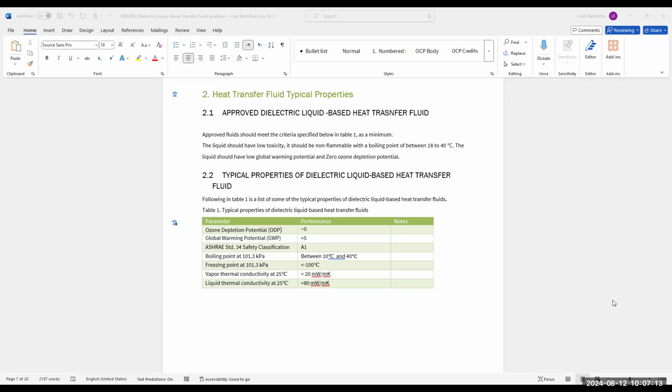Depending on the application, immersion will go for 40, even for 50. And we will select probably something in the 20s that will give us a range of boiling temperatures of 30 to 50. That depends on the chip, the GPU or CPU that we're cooling.